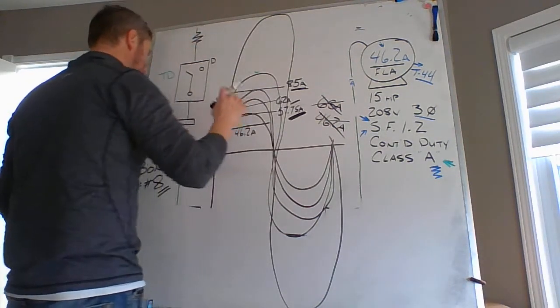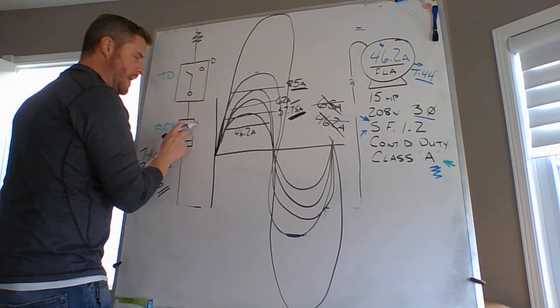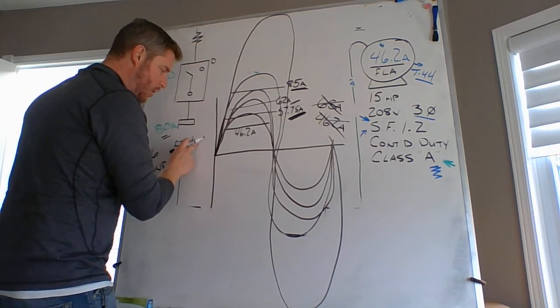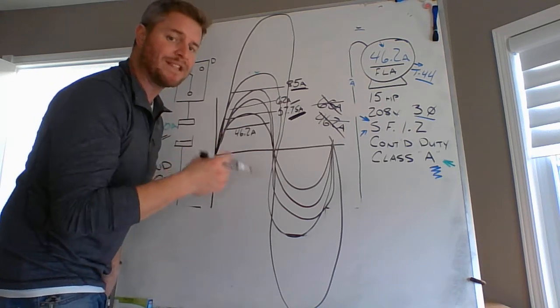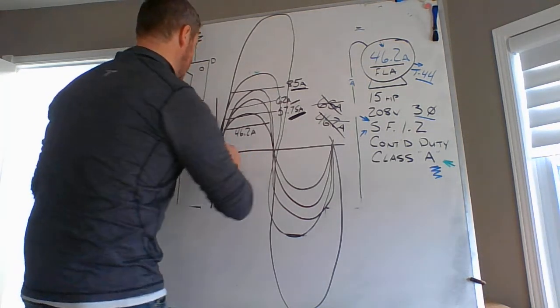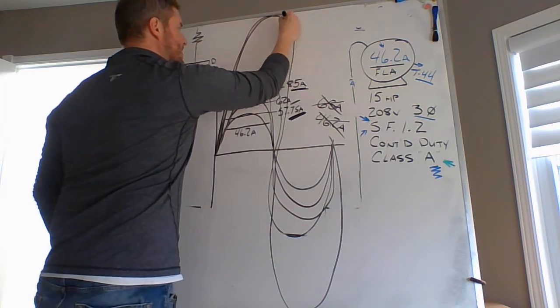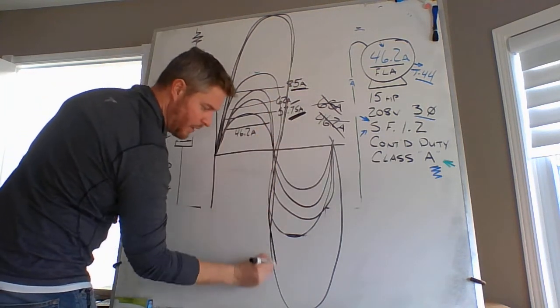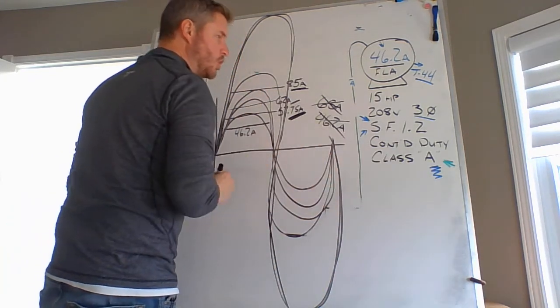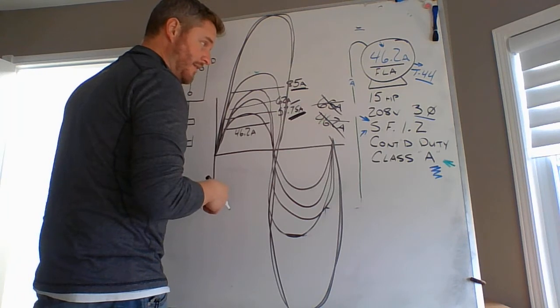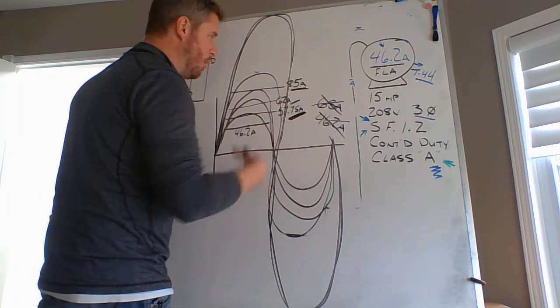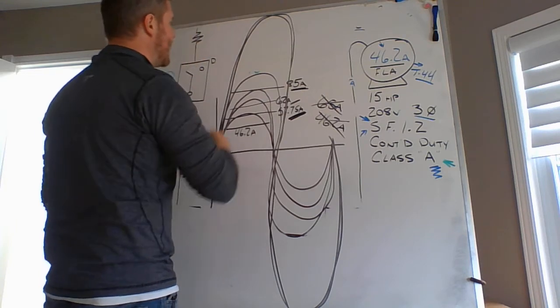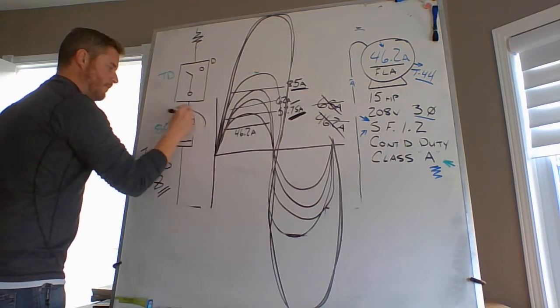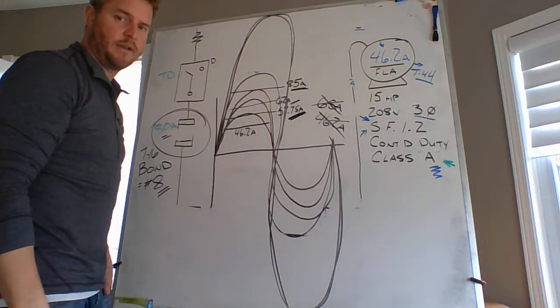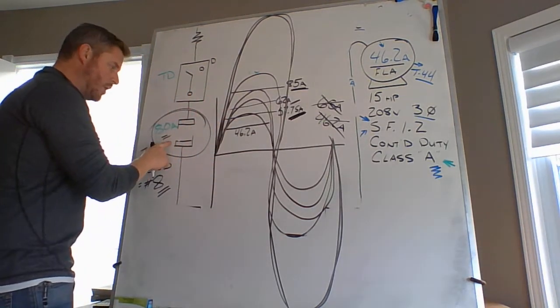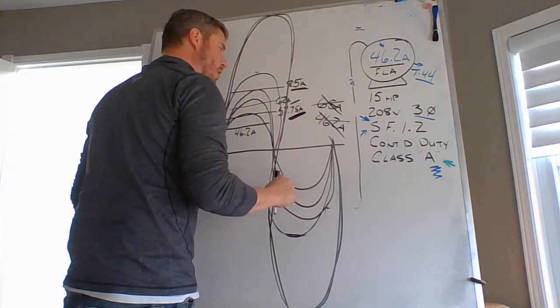And once you draw an exponential amount of current, this time delay or the non-time delay or the fact that it might be a circuit breaker doesn't matter. It opens as fast as possible because you are seeing an exponential increase in current flow along this AC sine wave. Exponentially. This could be all the current that would flow before your conductors melt, your fuses blow, or your motor explodes. Exponential amounts of current. But what's going to stop that? This overcurrent device. So that's exactly how your overcurrent device protects the fault that's in your motor.